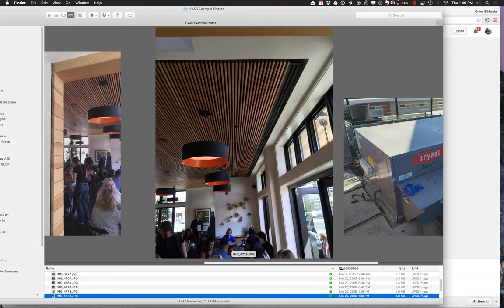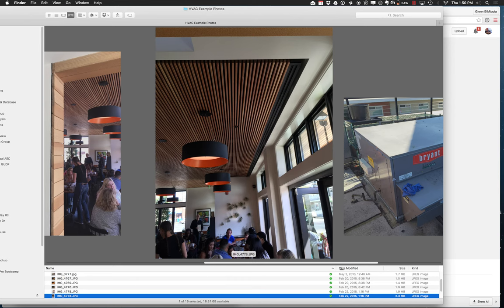This is a restaurant in San Carlos with a very interesting ceiling. Can you spot the HVAC system? It's right down here — these linear slot diffusers. There's not very much area per foot, so you need a lot of footage, but it makes for a very even distribution system and blends in architecturally. They have this slotted ceiling with little air diffuser slots that just blend in very nicely. When those doors aren't open, air is supplied over here, comes down past the glass — which will be hot or cold — and then exhausted back up to the center.